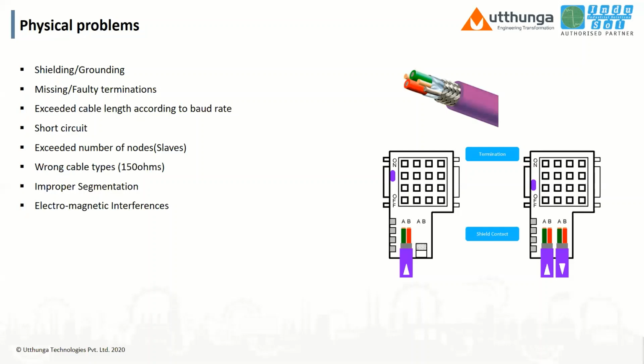Exceeded number of nodes or slaves: in a single segment, the maximum number of Profibus nodes that can communicate is 32. If we exceed that limit, communication will get interrupted. Then wrong types of cables. The standard impedance for a Profibus cable is 150 ohms. So if we use a different cable or a low standard cable, your communication will get interrupted. Then improper segmentation and electromagnetic interference. Electromagnetic interference is mainly caused by the drives. Drives are mostly used in Profibus networks, like high consumption devices, so usually EMI effects are in the drives part.